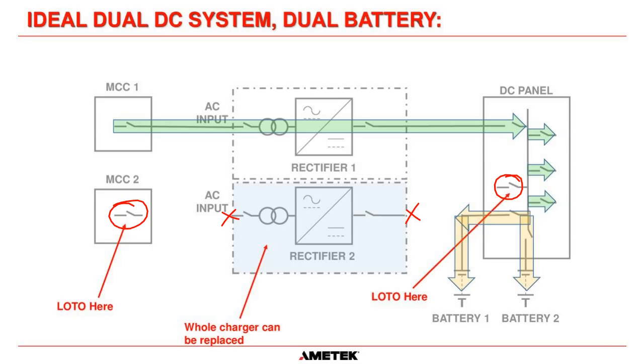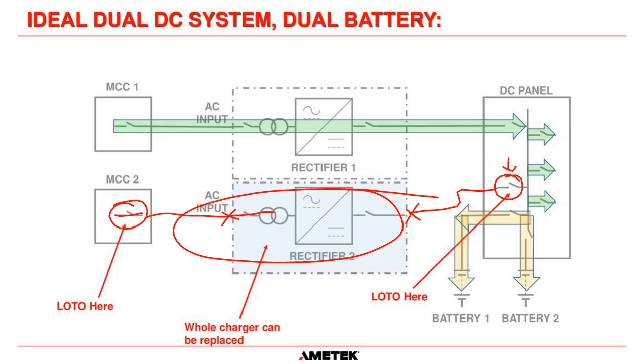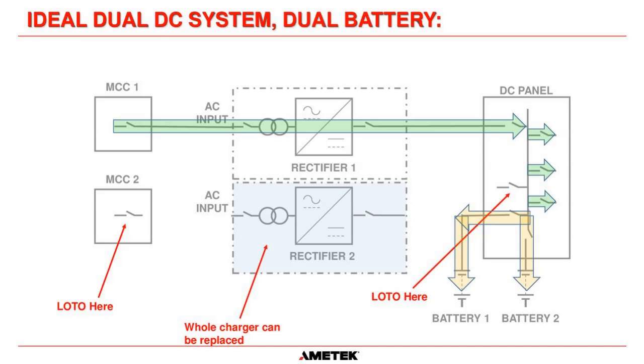Once charger 2 has been replaced, we can connect the cables, remove the LOTO from MCC2, and energize the charger, keeping this breaker here open, and we can do all the testing on this system. Then once everything is okay and the cables are connected, the last thing we would do, knowing that the charger is okay, is close this breaker here. So you can see the load circuits won't be affected. You don't need to do this in a turnaround. You don't need to wait for a plant outage. When you have a parallel redundant system, you can easily replace a charger without affecting the load circuits whatsoever.